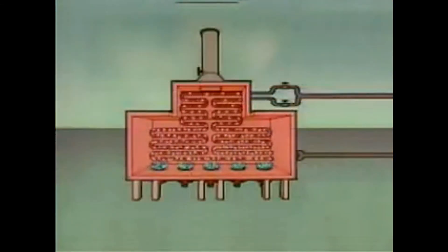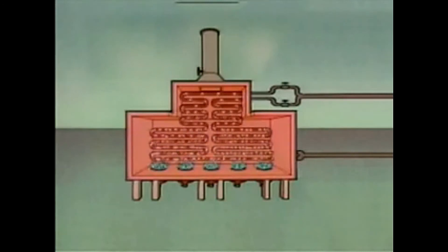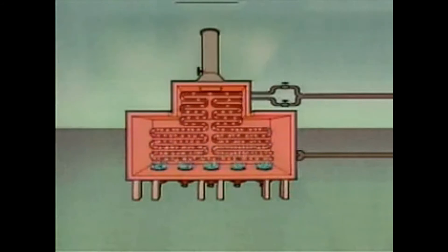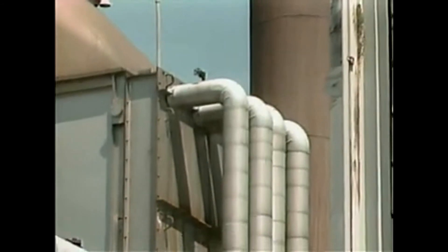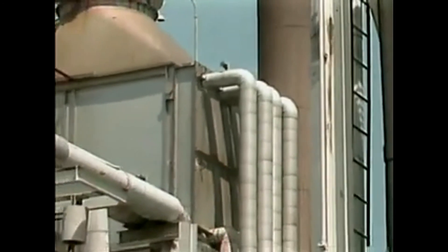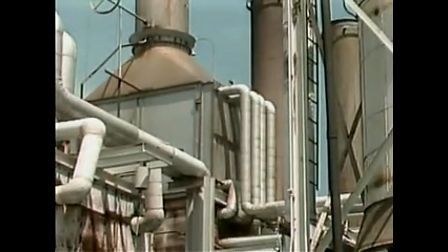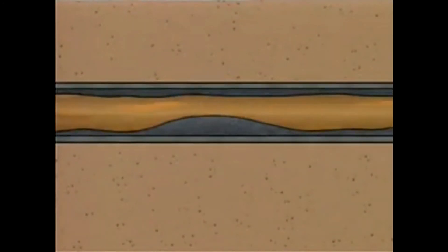In multi-pass furnaces, the flow of fluid through the tubes can present additional problems. In addition to flowing at the proper rate, the process fluid should move evenly through all of the tubes in the furnace. If the flow is not even in all the tubes, the fluid will not be heated evenly, and the temperature of the fluid leaving the furnace may not be within the specified range. Also, if the process fluid moves too slowly in a furnace, the likelihood of coking and its associated problems could increase.